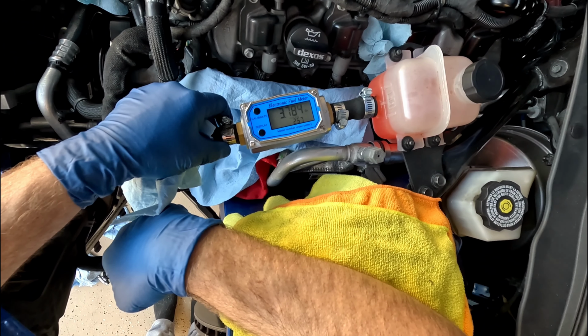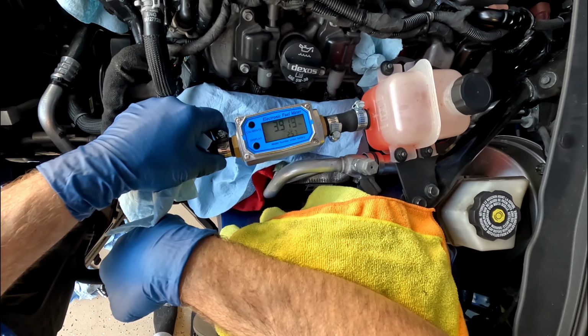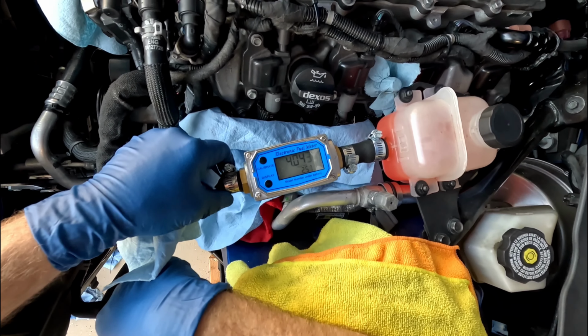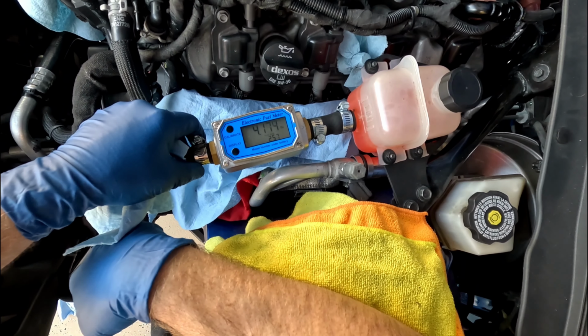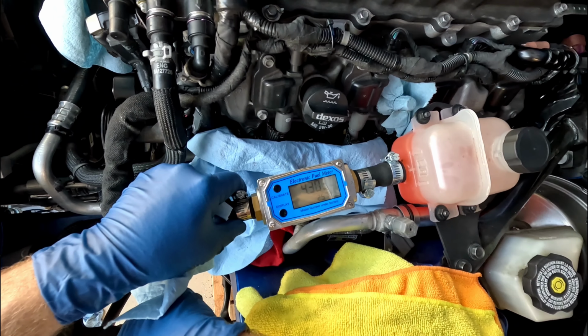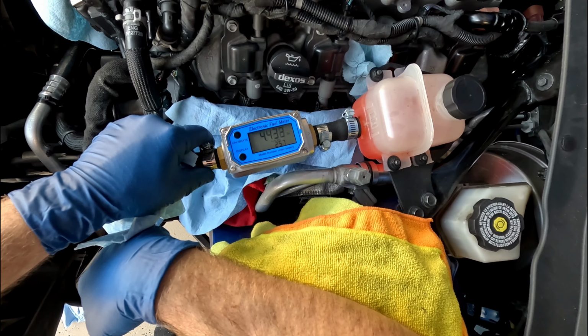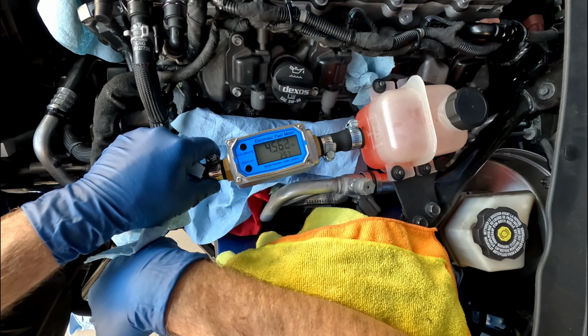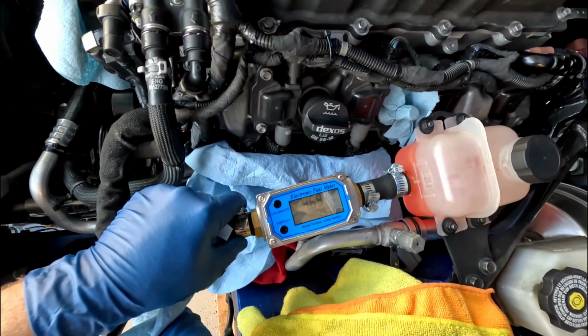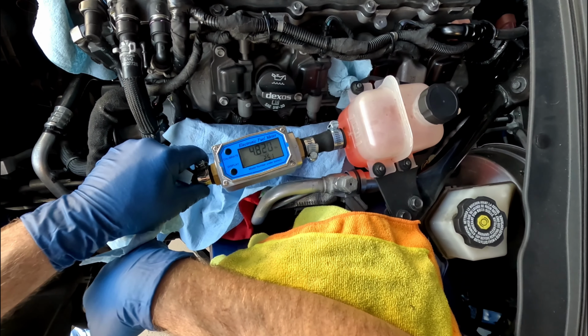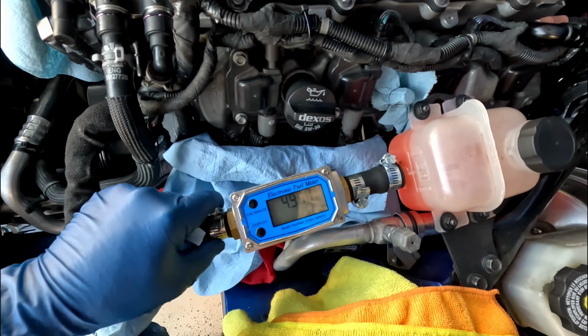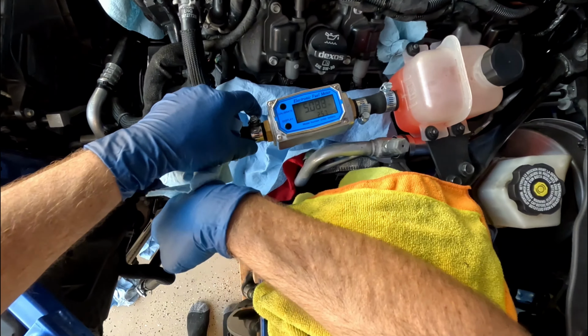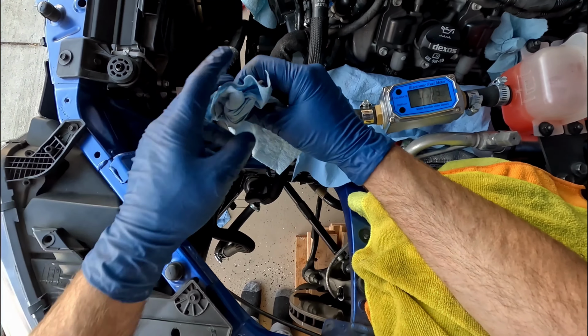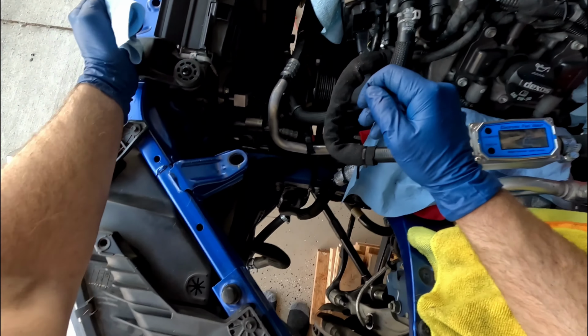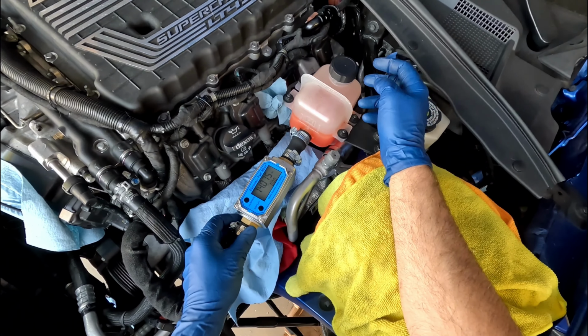So I bumped it up to 1, which was the same as my buddy Gabe, and now it seems to be flowing around what it should be. So his K factor was 1.00, mine was set at 0.05, which I believe meant I was only reading 5% of the flow. Now that I bumped it to 1, it's looking at a little bit over 2.5 gallons, and this is on the stock pump. Basically all the stock lines except for a couple little pieces of 3/4 to get this all plumbed in. Alright, now it seems we've got that figured out.